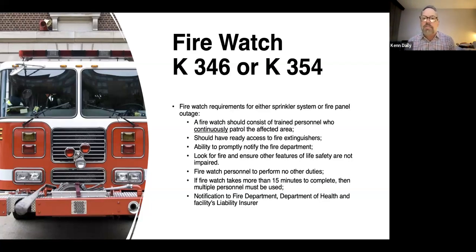Now, fire watch for your fire alarm system is KTAG 346, and your fire watch for your sprinkler system is 354. Either way, the individual doing the fire watch, the fire watcher, is doing nothing else but the fire watch. They have a singular job, continuously patrolling your building, ensuring that there's no fire breaking out, and they have had some training and testing. That training would be like, do you know what fire looks like? Do you know what fire is? Do you know how to call 911? Do you know how to use a cell phone? Do you know how to carry a fire extinguisher? Do you know how to walk around a building? So you're giving them some basic instruction, and then they have no other duties.